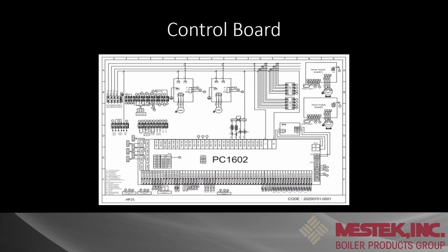So on the control board, I'm not going to get into everything on here, but I will tell you this, it's pretty impressive that every one of these lower inputs, whether they're sensors, pressure switches, whatever they are, is labeled. Let's just say we did have a bad pressure switch. It comes up on the board as a fault. We're able to look at that fault and say, oh, okay, it's inlet water temp. It's going to have that labeled on that wire, so you're able to trace it right back to where it is. So it makes troubleshooting pretty simple on that side.